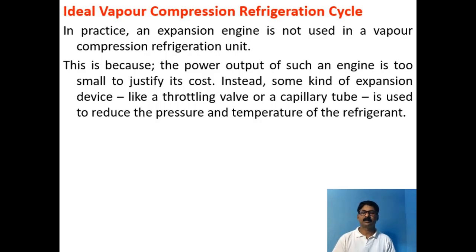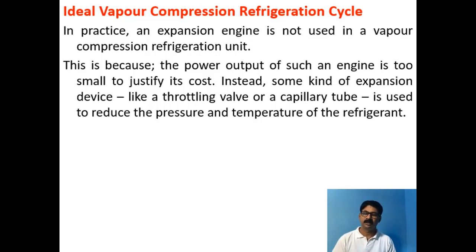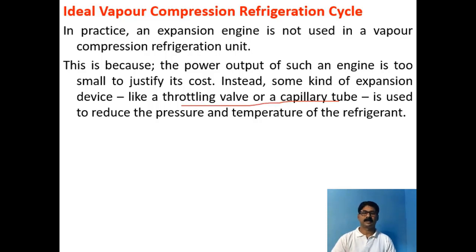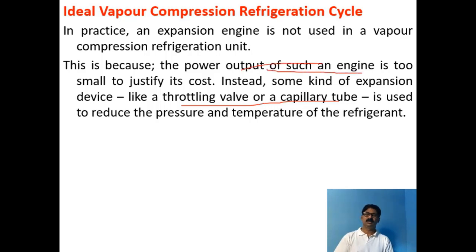In practice, the Expansion Engine is not used. Instead, we use an Expansion Device called a Throttling Valve or Capillary Tube. The purpose of this Expansion Device is to reduce the pressure and temperature of the refrigerant. Before passing it through the evaporator coils, its temperature has to be below that of the space to be cooled. The reason the Expansion Engine is not used is that its power output is too small to justify its cost.